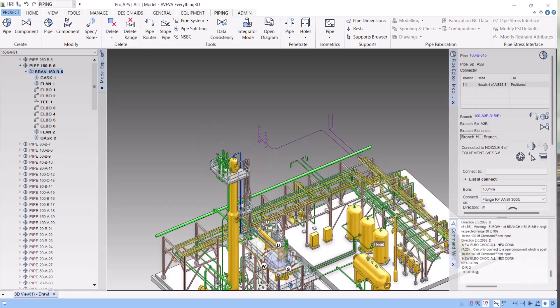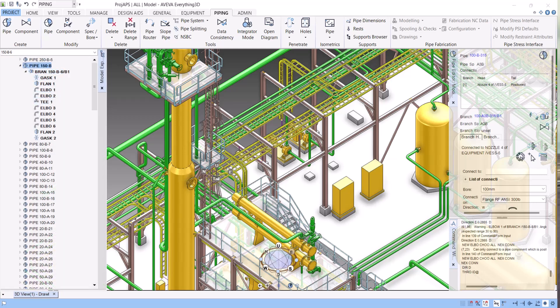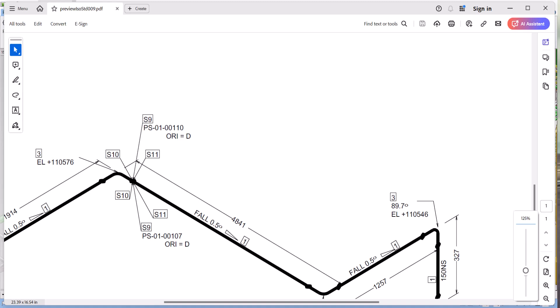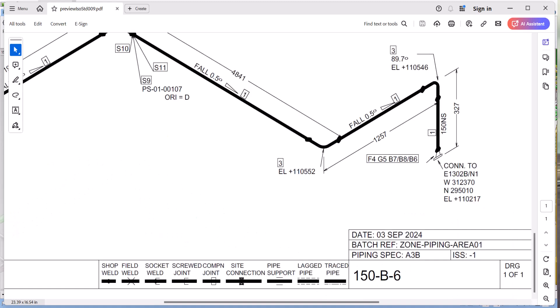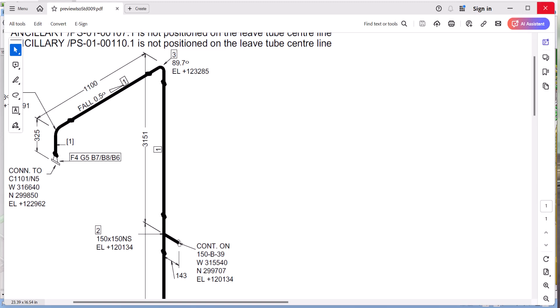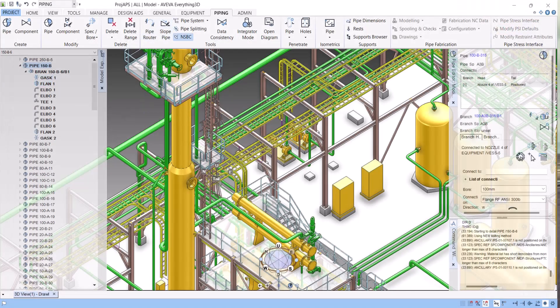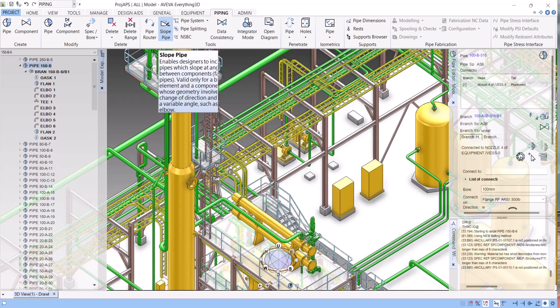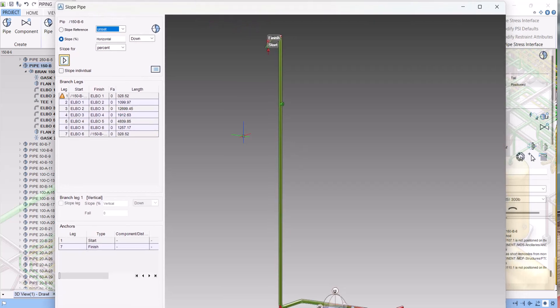Now we will run the isometric and see how the slope looks in the isometric. You can see here the slope is given — this side, this one, and the top also — so this is perfectly all right. In E3D there is also a built-in slope option. However, there is a limitation: you can give slope only to a single pipe. If you have any accessories, drain, or something else it will not land properly. When you click it, a window will open called 'Slope Pipe' where you can see types of slopes — 1:200, 1:50, 1:75, 1:50, 1:40 — and you can see the angle for each.